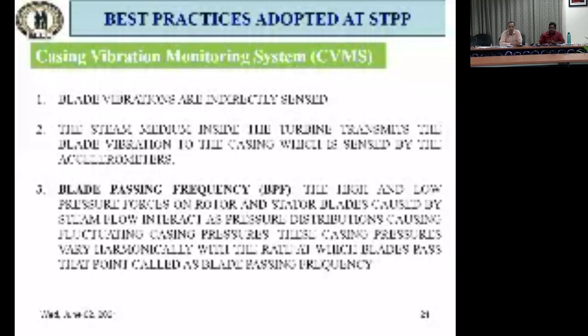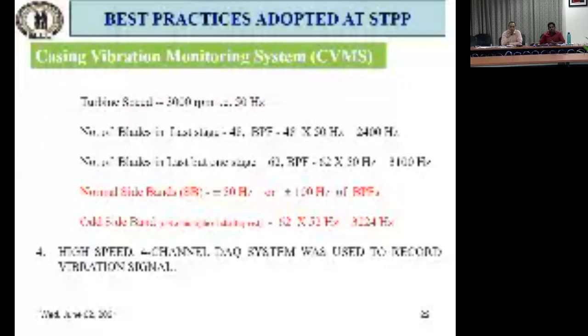What we got done is the casing vibration monitoring system, which measures the blade pass frequency of the last two stage blades, the 7th and 8th stage blades. So we have measured that. When it is running normally, the last stage blade has 48 blades, so 48 into 50 is 2,400 hertz, and if the frequency comes to 2,400 hertz, it is okay. The last-but-one stage blades are 62 into 50, 3,100 hertz. If the frequency is recorded like that, then your blades are okay.